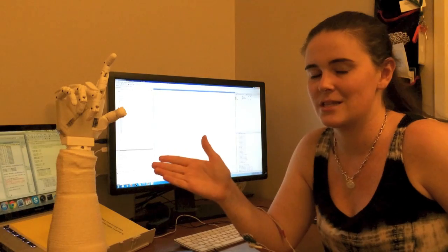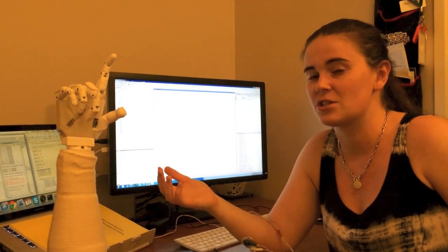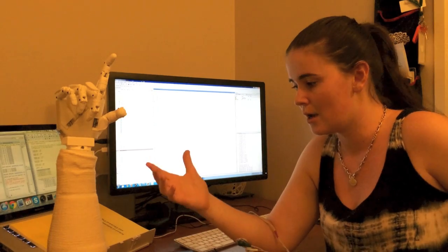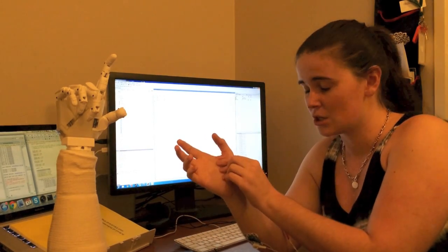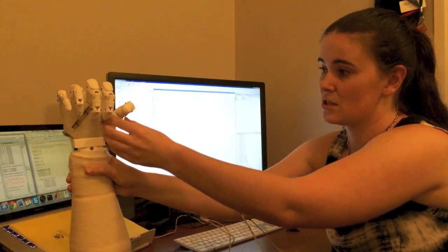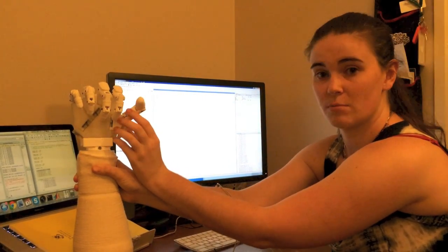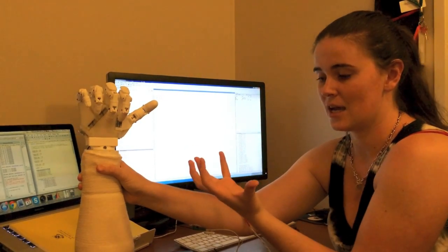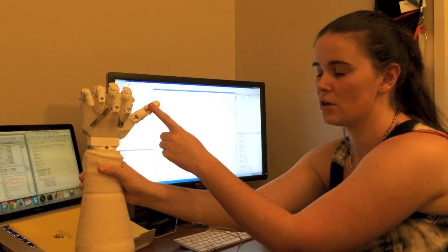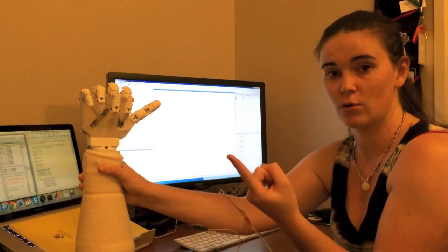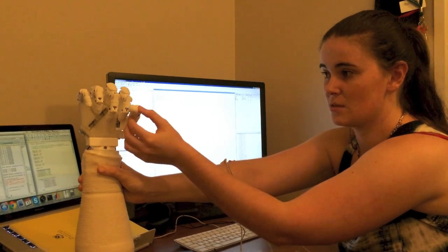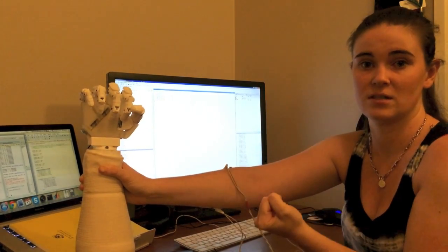So what you see there, this mapping of different gestures, is actually how current commercially available prosthetic hands work. The thumb acts like a switch in the commercially available products. The patient locks the thumb to a certain position, and that acts as an indication of how they want the hand to close. So if it's locked into this position, it means I want to make a point when you get activation from these muscles. But if it's locked into this position, I want you to make a fist instead.